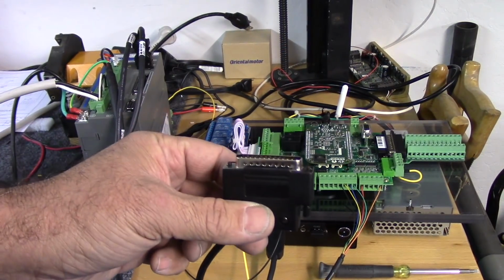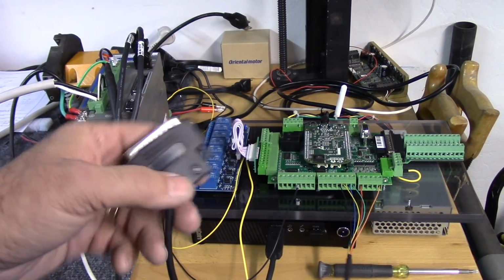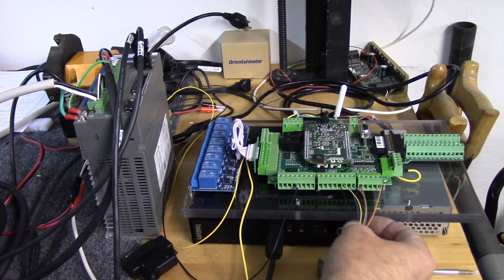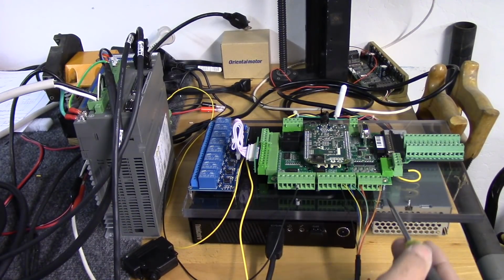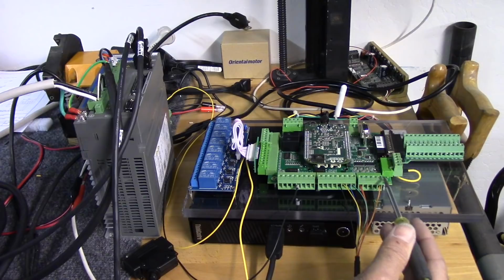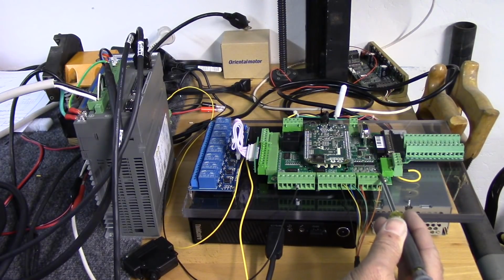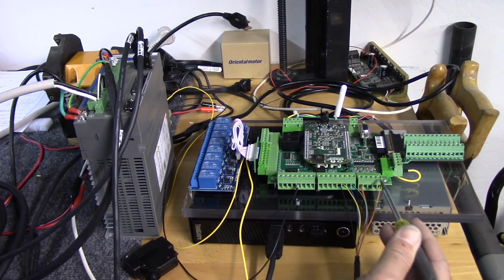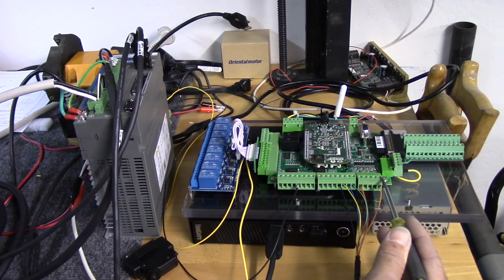So here's the DB25 end of it. Here's the flying leads from the cable. And what we've got here, this orange wire is going to input 5, IN5. This is the drive fault. If you have 3 or 4 DYN4s or 2 DYN4s, all the orange wires will go to input 5. This is fault. So if any one of the drives fault, it will close this input. Input 5 must be set to normally open in the wizard.